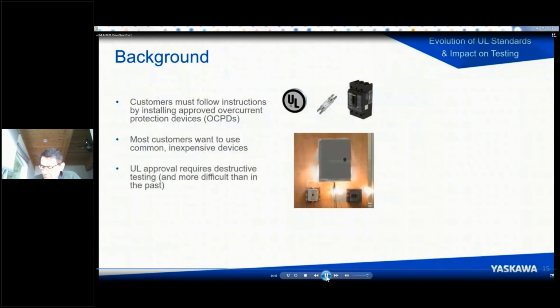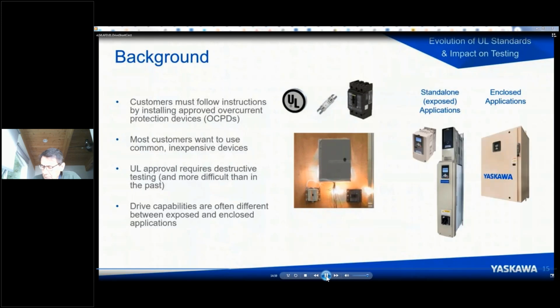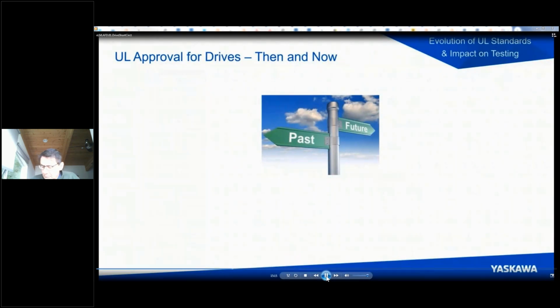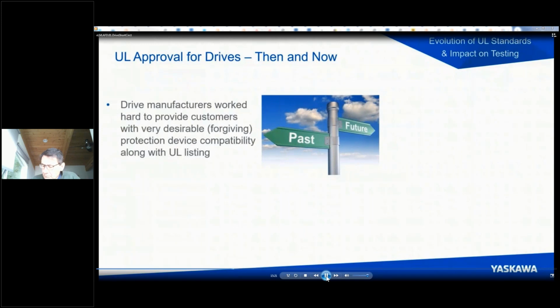But UL, in contrast, requires us and other drive manufacturers to do destructive testing. And this testing has become more difficult than in the past. And so what happens is the capabilities, the result, is often different between drives that are exposed and enclosed.